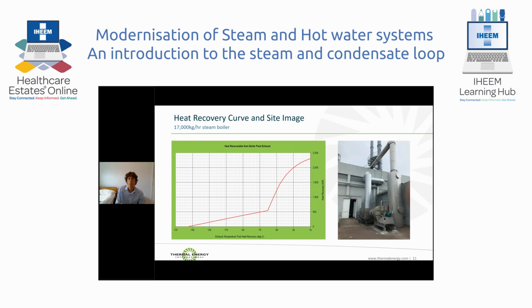This is a typical heat recovery curve for a gas-fired boiler. This is a 17-ton boiler. As you can see at the bottom part here, we've got a linear increase in energy recovery as we reduce the temperature. This is called sensible heat recovery. Around about 60 degrees C, we reach an inflection point where the heat recovery increases significantly. This is the wet bulb temperature and marks the point where, as we cool the exhaust, we start to get condensation. And this is where we can recover a lot of additional energy through a direct contact condensing heat recovery system.